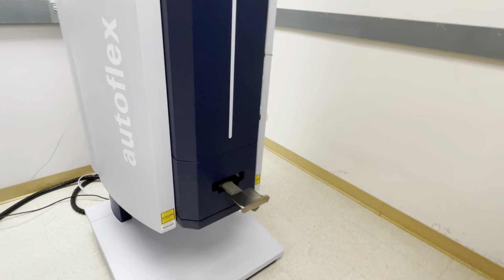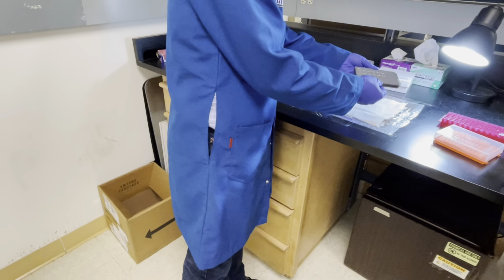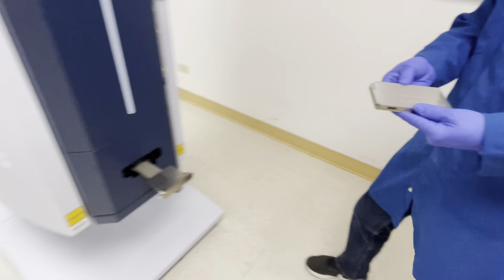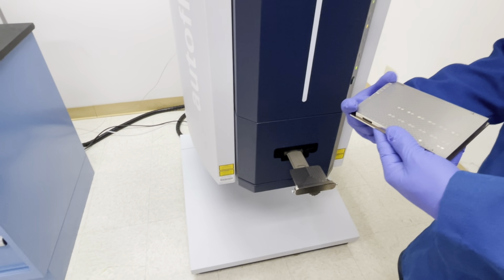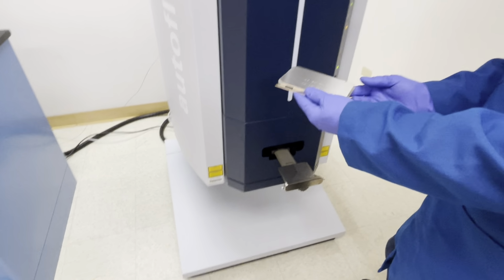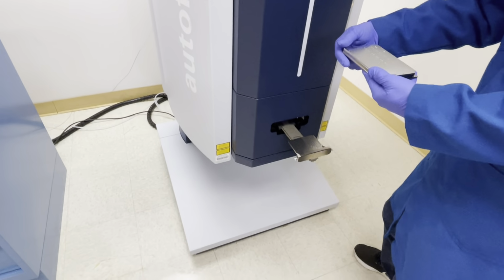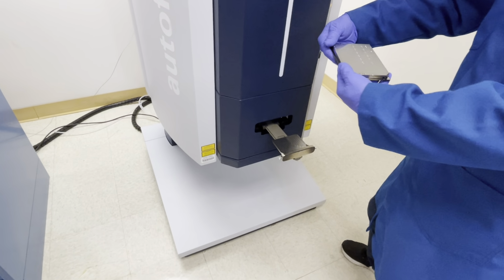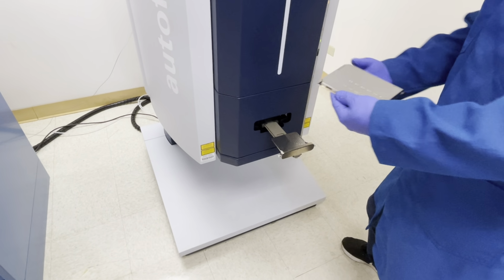And again, you don't necessarily need to wear gloves. Hold the plate, be careful, don't drop the plate. And right here, you see, you have an angle. This angle needs to face in. Otherwise, if you do something like this, it's going to mess up everything and damage the instrument. So make sure the angle needs to face in.